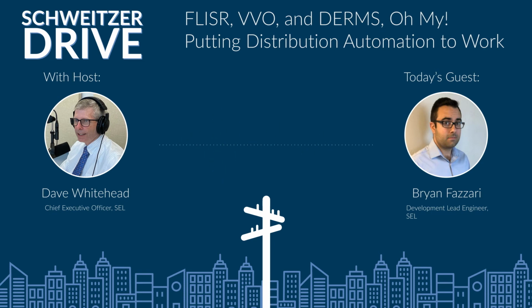But power no longer flows just from the substation. This is not only interesting as an automation or protection engineer, but it has safety connotations as well. When you trip the breaker at the substation, is the power off? Can a lineman go work on that? This is the same issue we're having with rooftop solar or anything else. Anywhere there's generation sprinkled throughout the distribution system, not necessarily under the direct control of the utility, there are all kinds of interesting technical challenges that pop up.